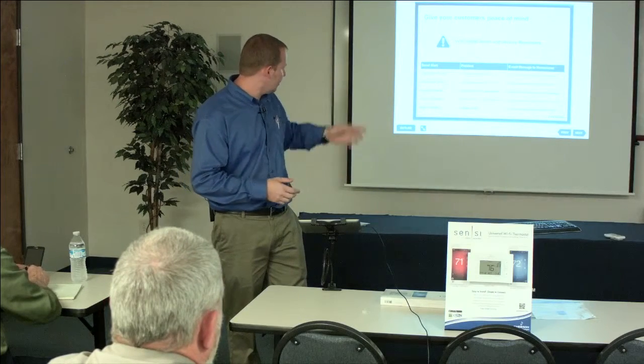So this is going to alert your customer whenever there's a problem. So you can see the alerts, but if you have a high home temperature, low home temperature, a loss of cooling, which is if it goes 5 degrees above set point, or 5 degrees below set point for heating, or high humidity, it's going to send an email message to the homeowner.